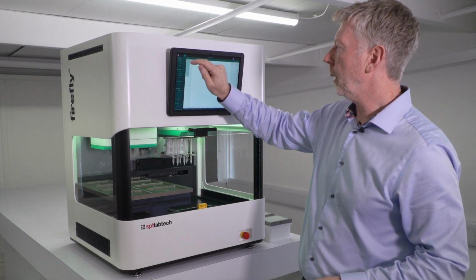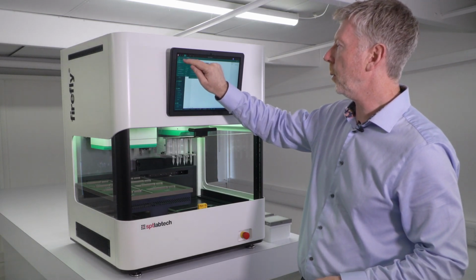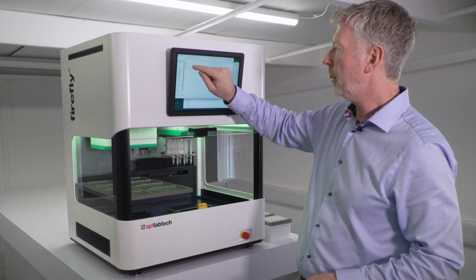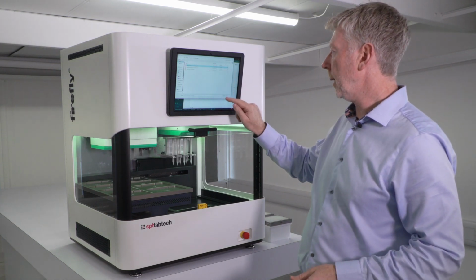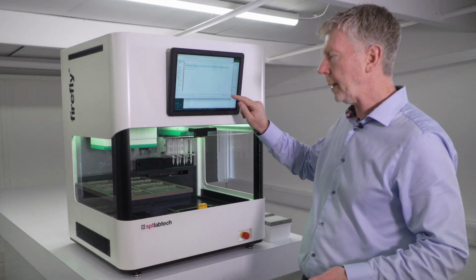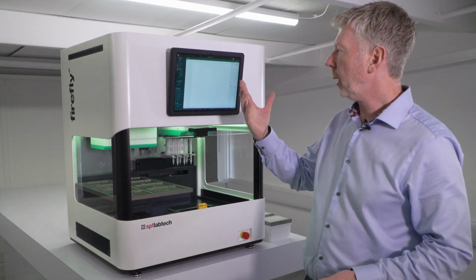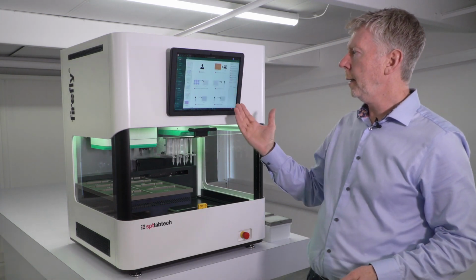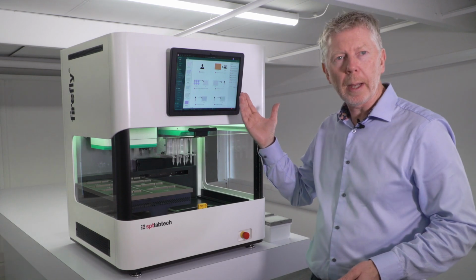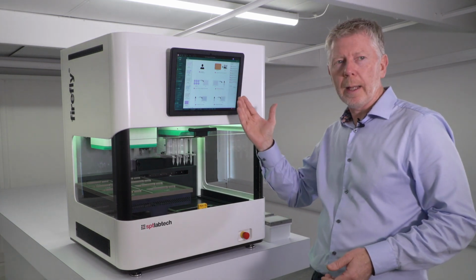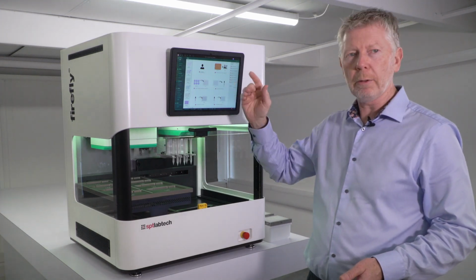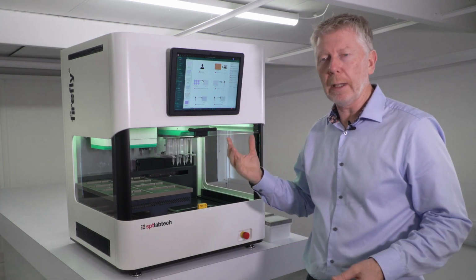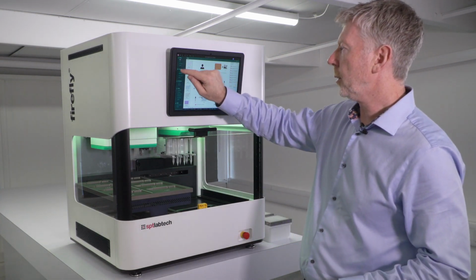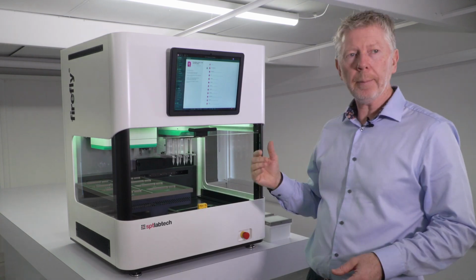I'm going to open a file, so I go to my folder on the computer. I'm going to open the demo protocol that I want to run, which is my PCR setup, and when I load that, I can see the steps and the programming behind this, but I'm actually going to skip by that for now and just go straight to the execute screen, which is where I'll go when I'm generally running this. So first of all, I can see a summary.